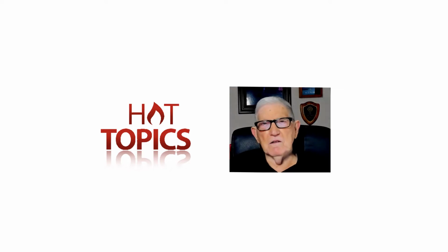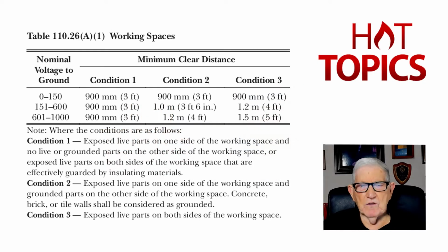Now, this was a two-part question, and the submitter wanted to know if the 5-foot maximum of your Table 110.26(A)(1) on page 50 could be used to default to the arc flash boundary? And of course, you should know by now the answer is no, you shouldn't do that.